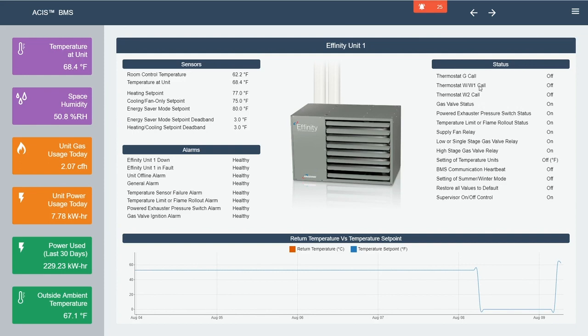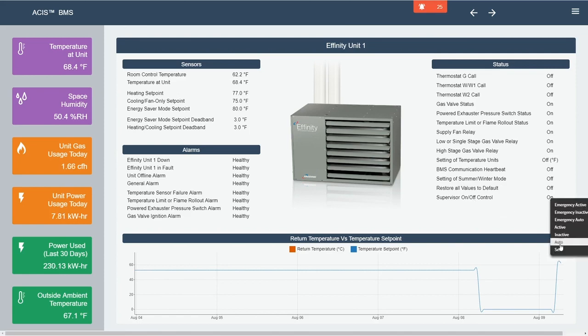You can still wire them in. Even though you're going to be running this unit off a thermostat, you still get the functionality of all the alarms, so you can still get the feedback. And also you have the option of a supervisor on off, so even though you're using a thermostat, you can still switch the units off via the BMS, which is obviously great for a customer if he wants to be able to shut everything down in one go.